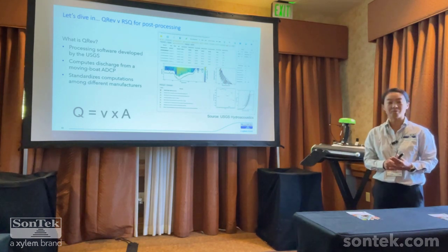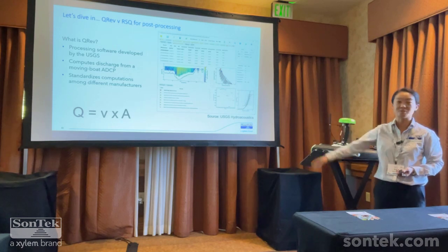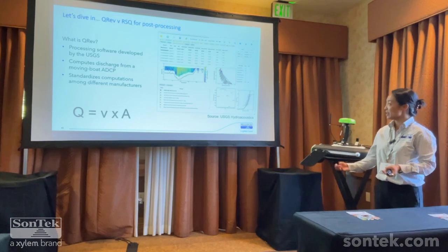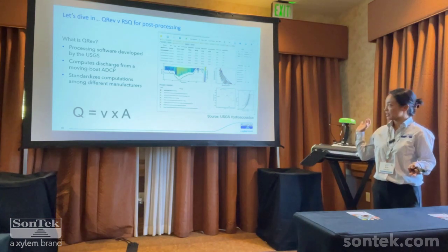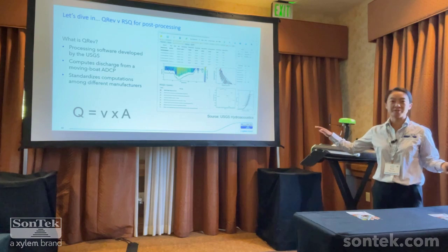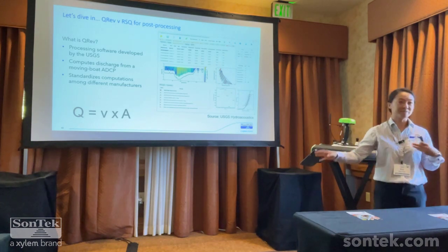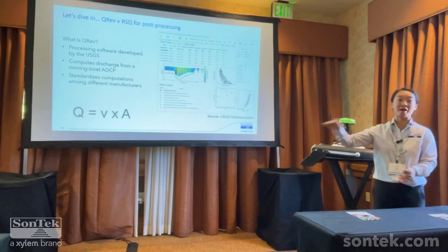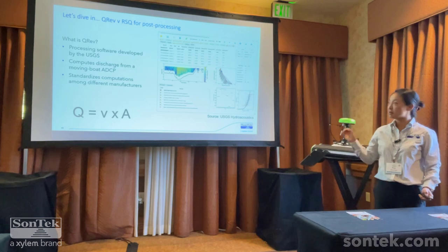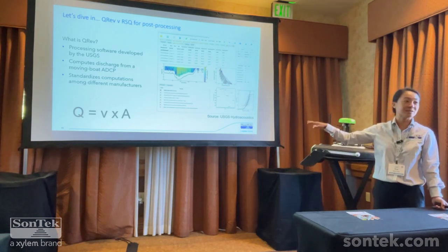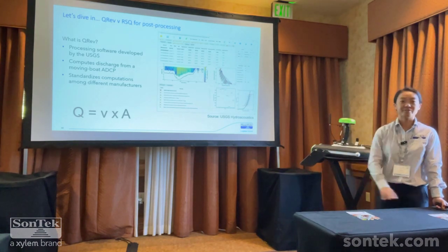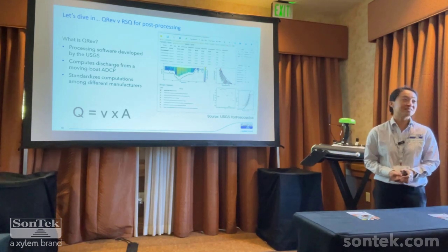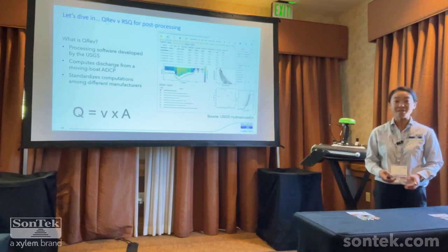You're going to see more and more organizations adopting QRev just because the USGS really made a lot of effort to normalize across the board all the different calculations and the different manufacturers of ADCPs in order to do things in the same way. There are so many different calculations and pieces that go into a discharge measurement that every company does it differently. And so this is an effort for USGS to really standardize the procedure.